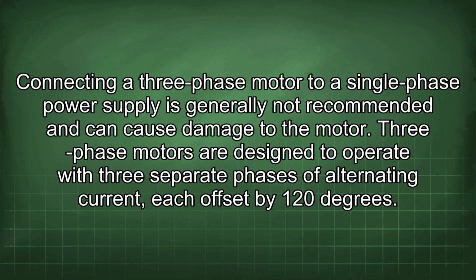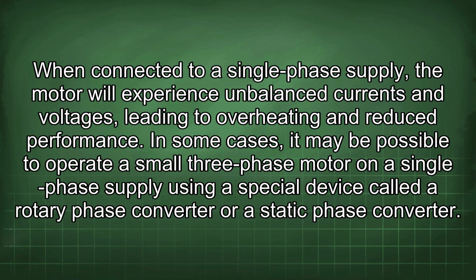Connecting a three-phase motor to a single-phase power supply is generally not recommended and can cause damage to the motor. Three-phase motors are designed to operate with three separate phases of alternating current, each offset by 120 degrees. When connected to a single-phase supply, the motor will experience unbalanced currents and voltages, leading to overheating and reduced performance.